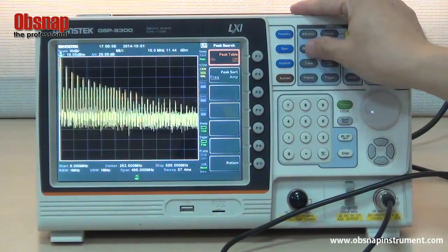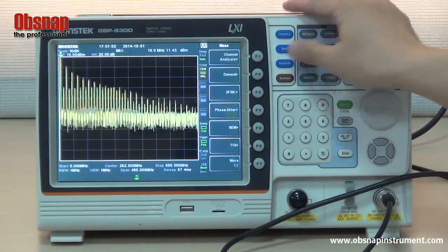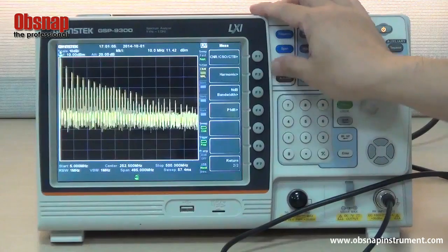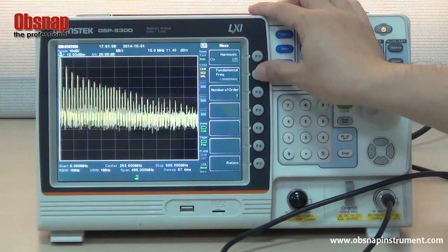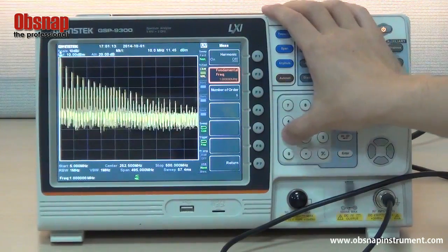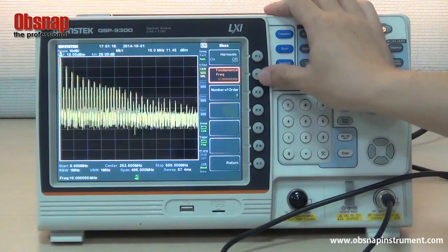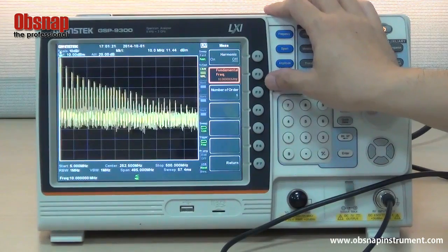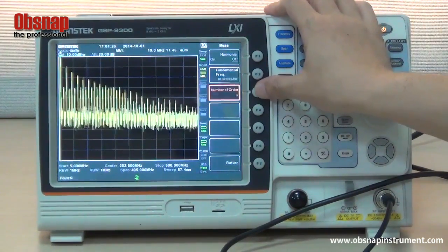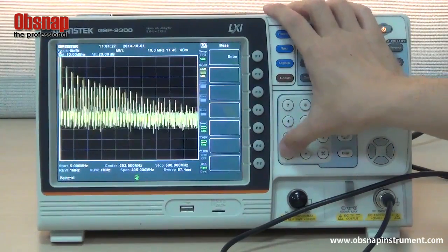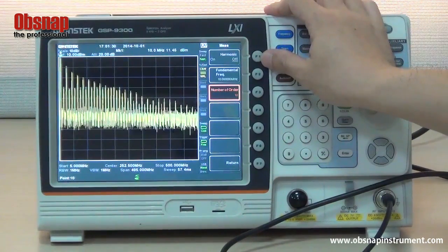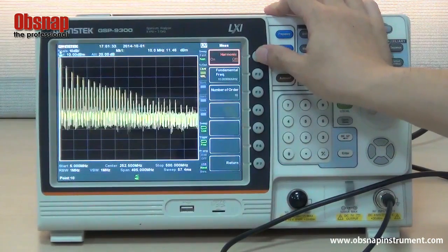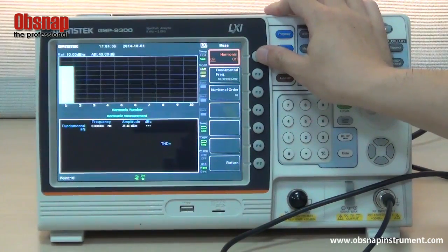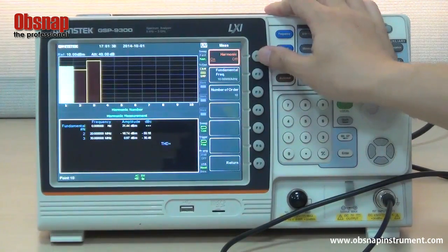Next, press measure, and F7, more, and F2, harmonic, and F2, fundamental frequency, input 10 MHz, to set the fundamental frequency as 10 MHz. Next, press F3, number of order, input 10, to set the order of 10. Press F1, harmonic, twice, to activate the harmonic measurement function.